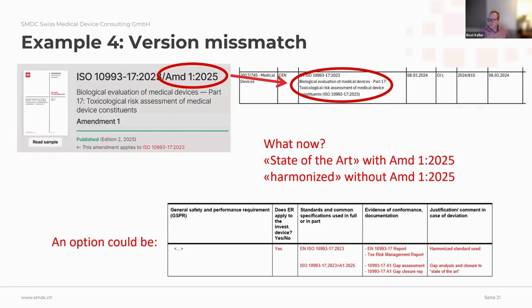answered, I see. Yeah, they'll still argue either way. It's a no-win when you get in a situation with the notified body that way. I'm just going to tell you, I've tried it both ways, and they'll still argue either way. You can have both arguments in there. It's state of the art. Either you have to have state of the art per the EU MDR, which is the newest standard, and you need to put both of them in there. In my opinion, this is also what I made the best experience with, having both in there. Daniel may have an opinion as well with his experience. And usually my experience will win out over the notified body evaluator, and I always opt to go up.